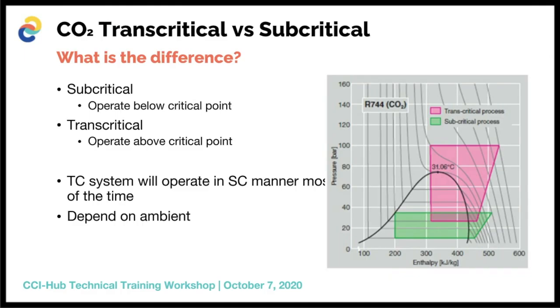Firstly, I would like to touch on CO2 subcritical versus transcritical operation. I have found that there sometimes is confusion about a plant being called a transcritical CO2 plant. The main difference between a subcritical and transcritical plant is just in the application, or how it is operating. For instance, a transcritical plant can operate in a subcritical manner when the ambient is cold enough to be below the transcritical point, which is 31 degrees Celsius.